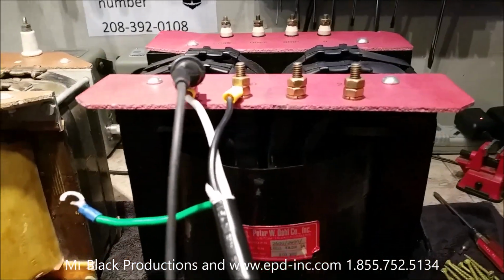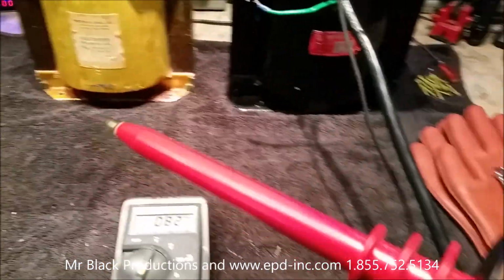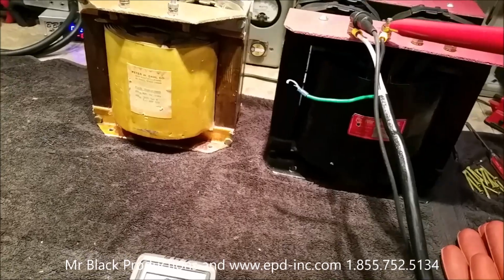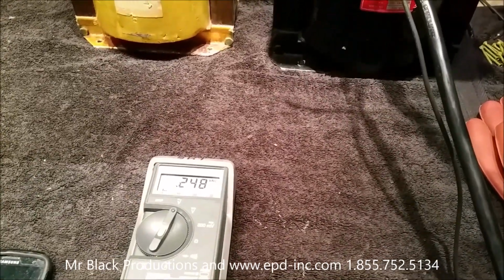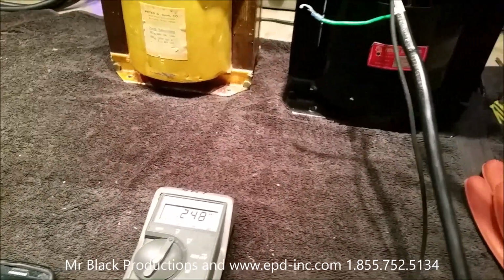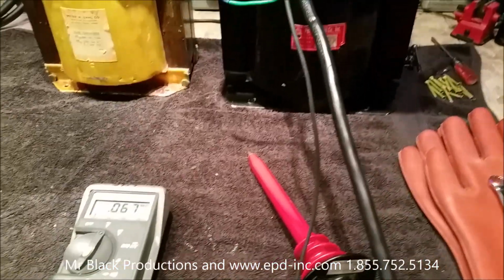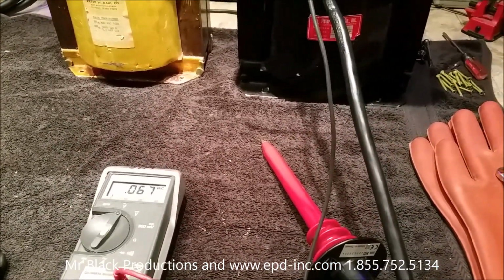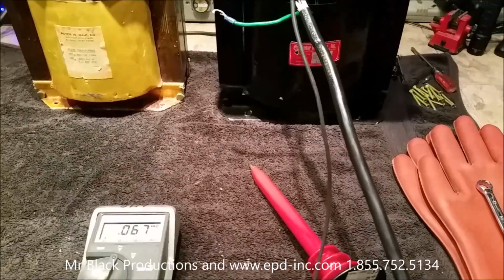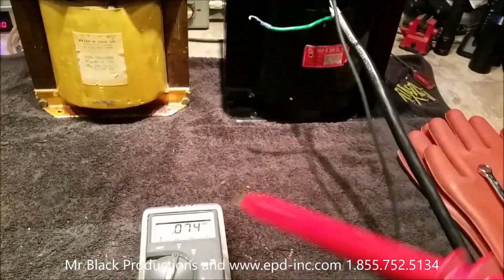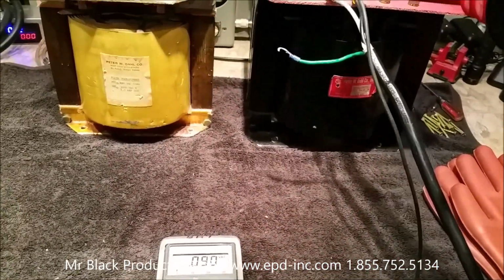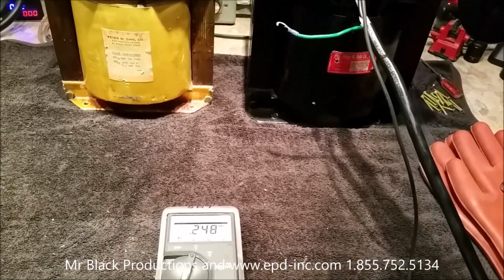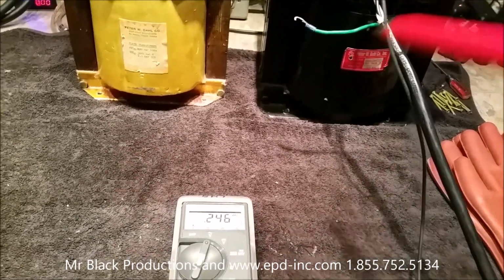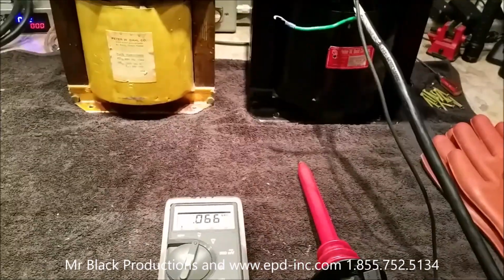Let's grab our probe, 10 to 1. Check our primary, 248 volts. Notice how electrically noisy that other transformer was, putting off eddy current and stuff. This one's so much cleaner that I can get an accurate reading on it. 248 volts, and what I've got coming in from the wall is 241.